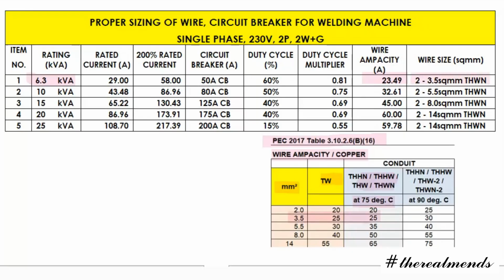Okay, so for the 10 KVA, we have 32.61 amperes. From the table, it pulls from here, 35 amperes. So our wire is 5.5 square mm. And then for the 15 KVA, we have 45 amperes. But looking at the table at 75 degrees Celsius, we have 50 amperes. So our wire is 8.0. Okay, so for the 15 KVA, 8.0 square mm. For the 20 KVA, we have 60 amperes.